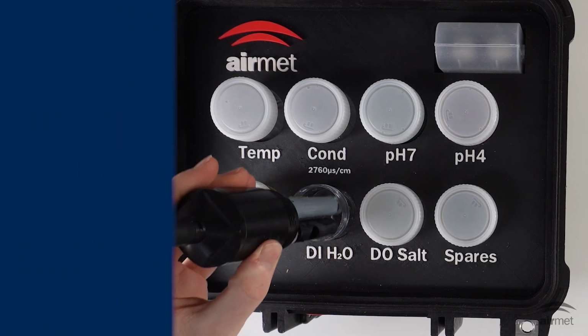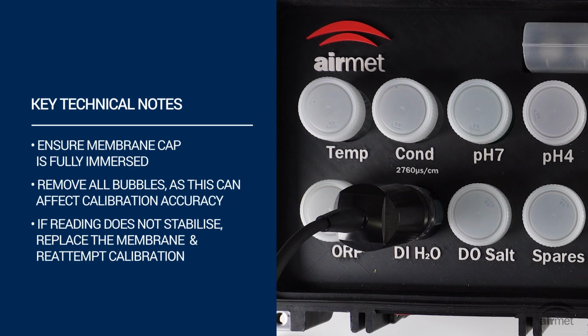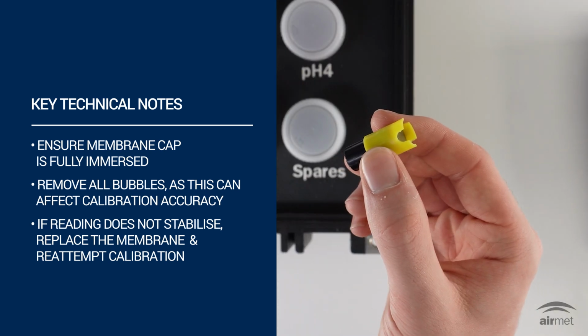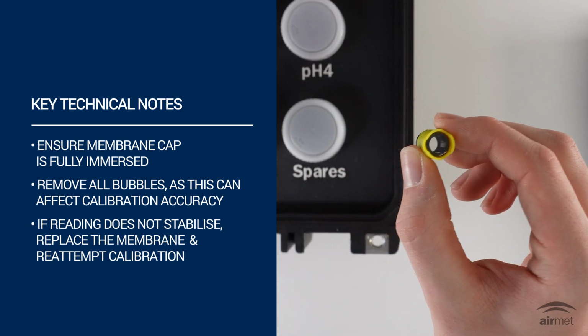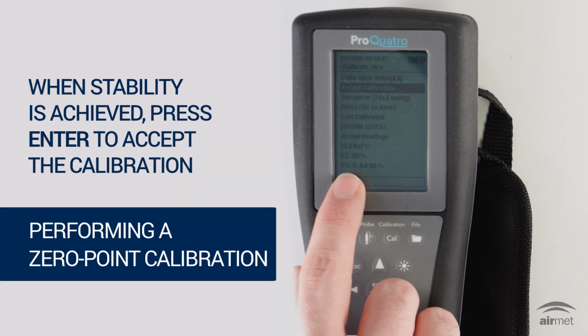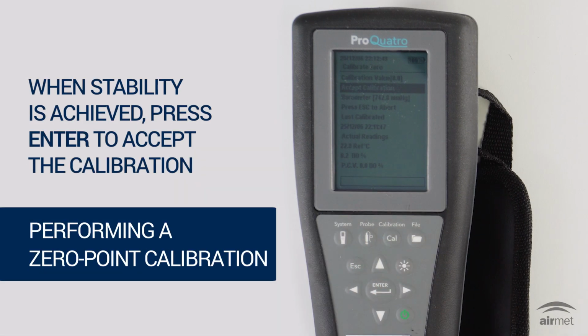Ensure the membrane cap is fully immersed. Remove all bubbles. Even tiny air bubbles can affect calibration accuracy. If the reading does not stabilize, replace the membrane cap and reattempt calibration. When stability is achieved, accept the calibration. The instrument will confirm success and return to the calibration menu.